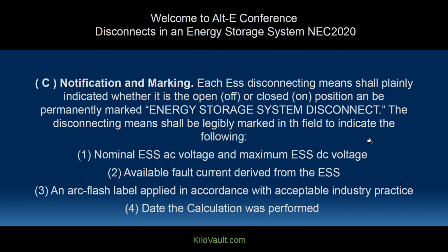Yeah, so you know how there's usually a big PV disconnect and usually an AC disconnect for the grid connection outside. Are you saying that there will also need to be an ESS disconnect out there too? Correct. That's the way things are kind of going at this time, pushing towards at this point. Some inspectors are requiring it, some are ignoring it. Right now with flooded batteries, yes, you're required, but with lithium and AGMs being below that 60 volts, theoretically, no. But there's also that part in the code that's requiring it for a disconnect to be external. So that comes into the interpretation of the local authority having jurisdiction, or your inspector saying yes or no to it. It's all the interpretation of the inspector at that point.